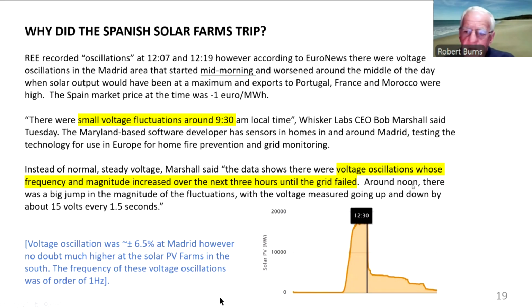And in fact, around midday, the oscillations were 15 volts up and down every 1.5 seconds. So that's 15 volts on a 230 volt domestic supply there. So the oscillation was thus plus or minus 6.5%. But it was probably higher at the wind farms, and I'll explain why a little further on. The frequency of these voltage oscillations was of the order of 1 hertz. So it's much slower than, of course, the 50 hertz stuff. It's a different oscillation.